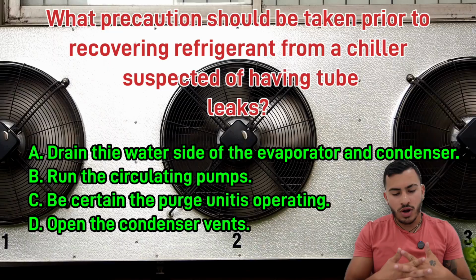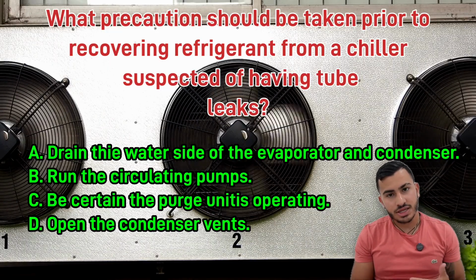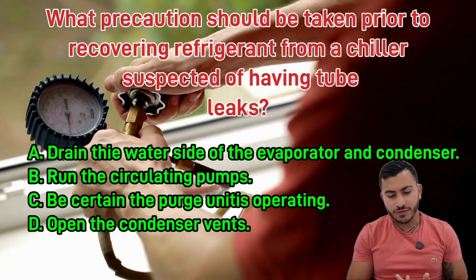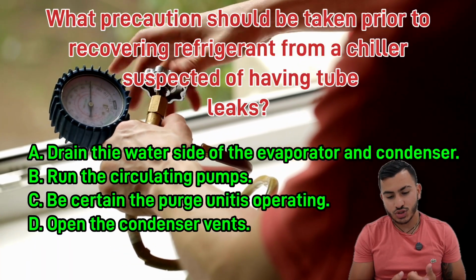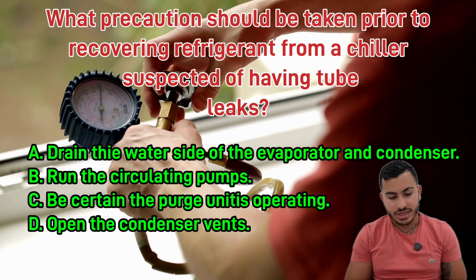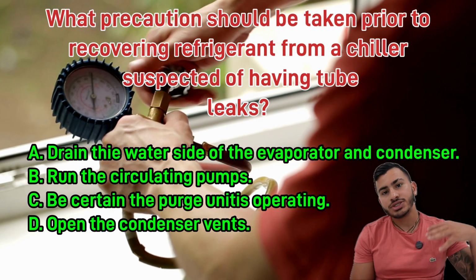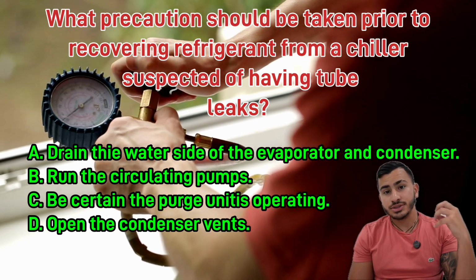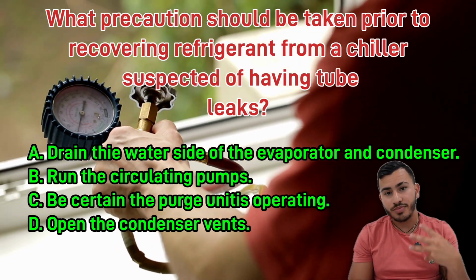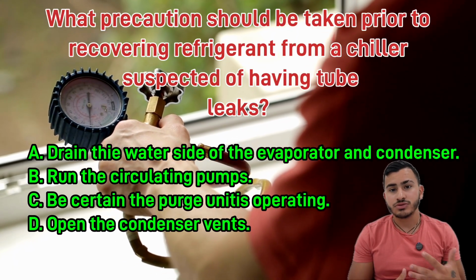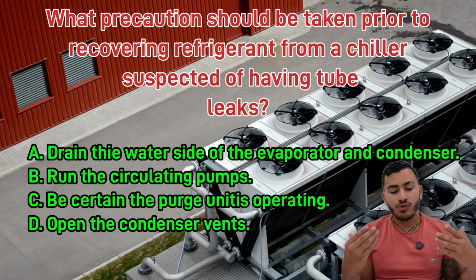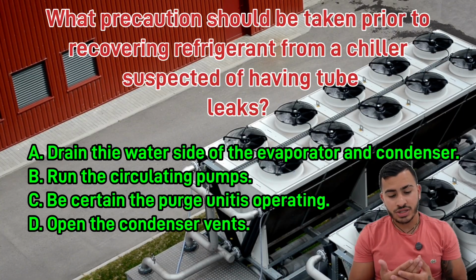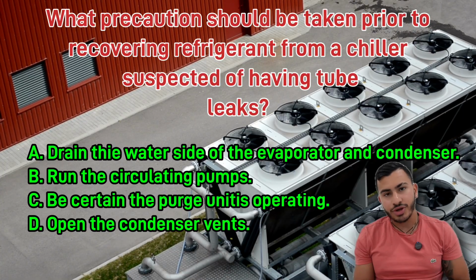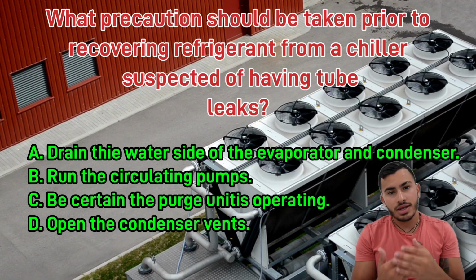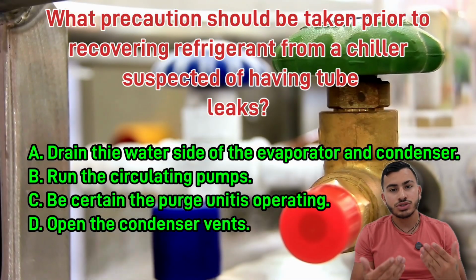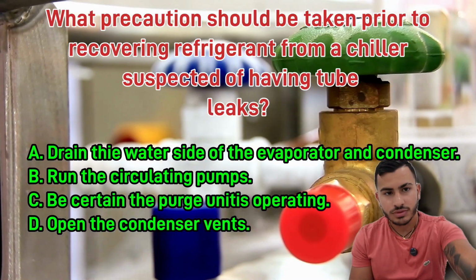Question number 4. What precautions should be taken prior to recovering refrigerant from a chiller suspected to be having tube leaks? Now, on a low pressure chiller with tube leaks, the tubes mainly have water. A chiller has water running through it, so the answer will be obvious in this one. Drain the water side of the evaporator and condenser. So A will be the answer for number 4.